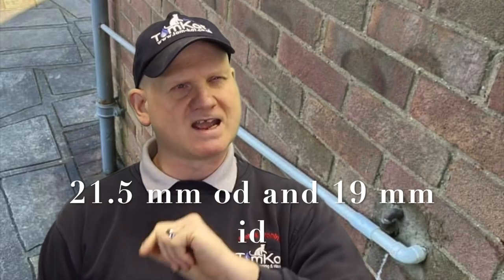So when it comes to having this condensate pipe installed, there are certain criteria the gas engineer needs to follow to make sure it complies with 1, the building regulations, 2, the British standards, but most importantly, 3, the boiler manufacturer's instructions.